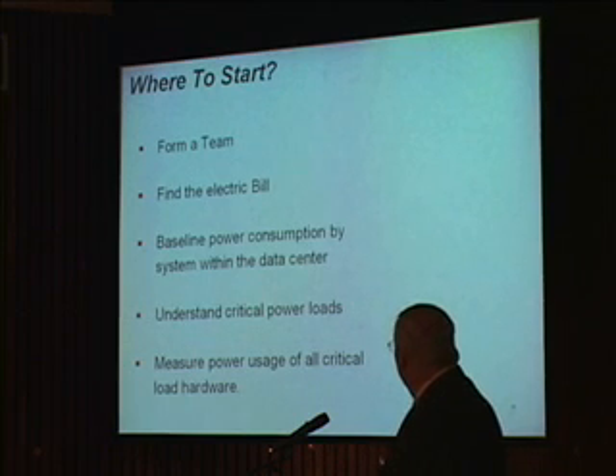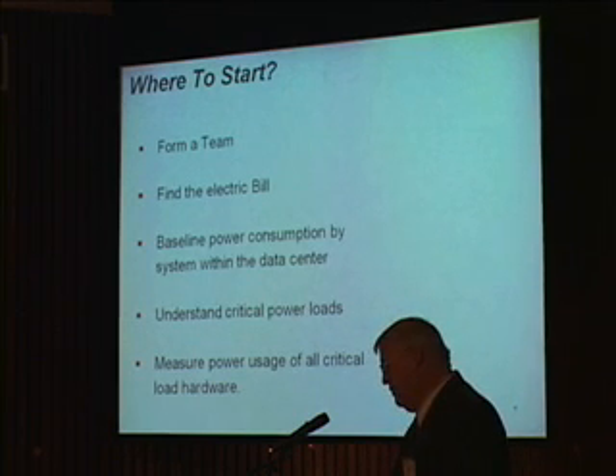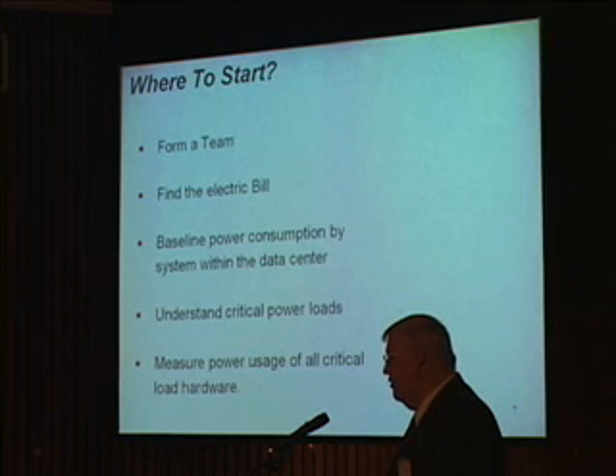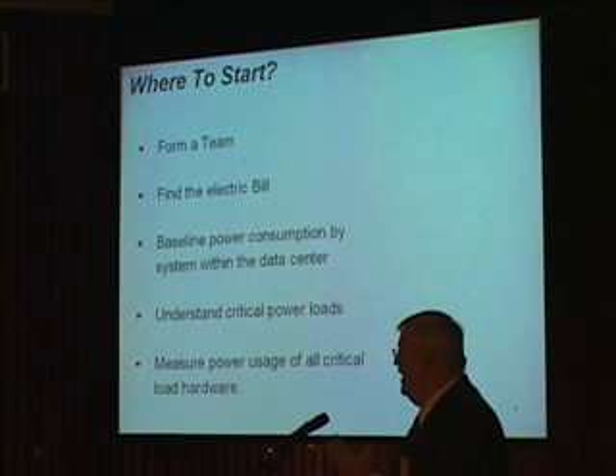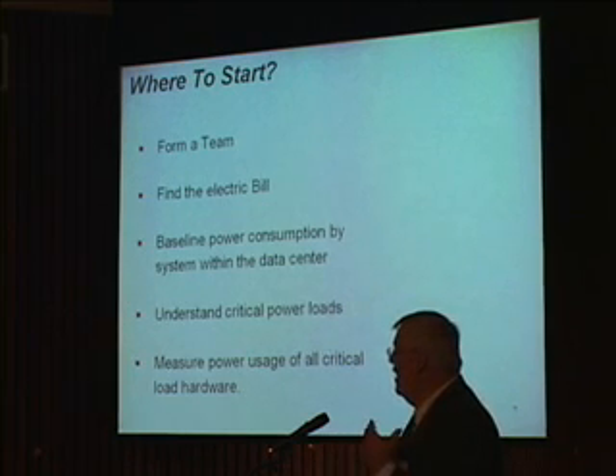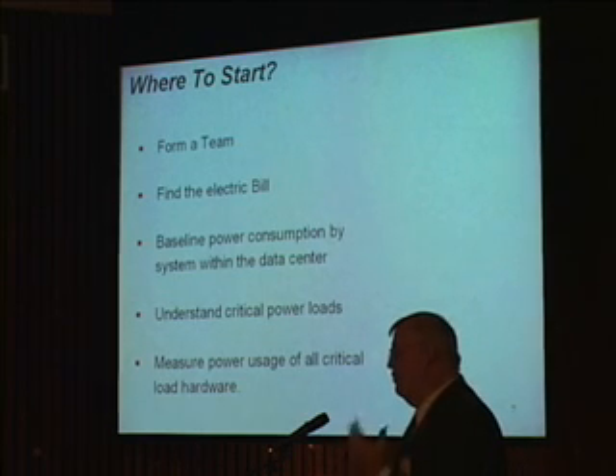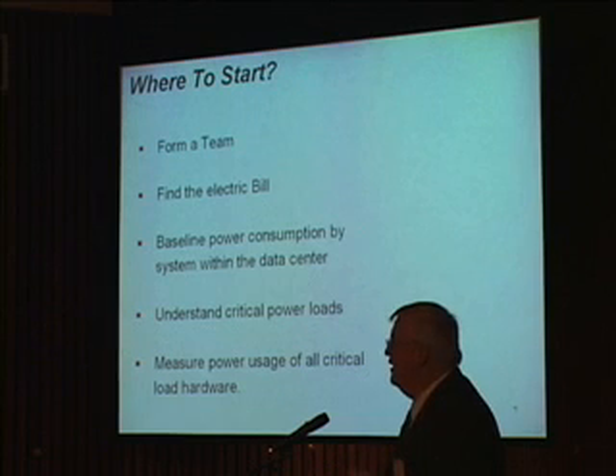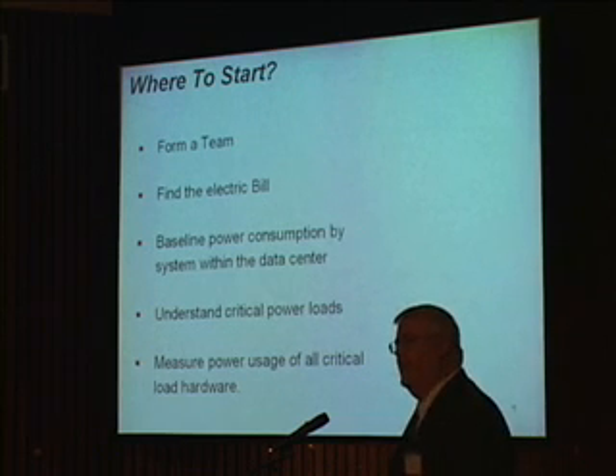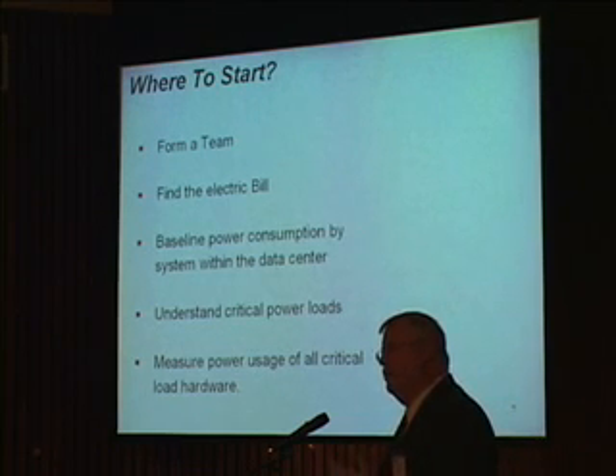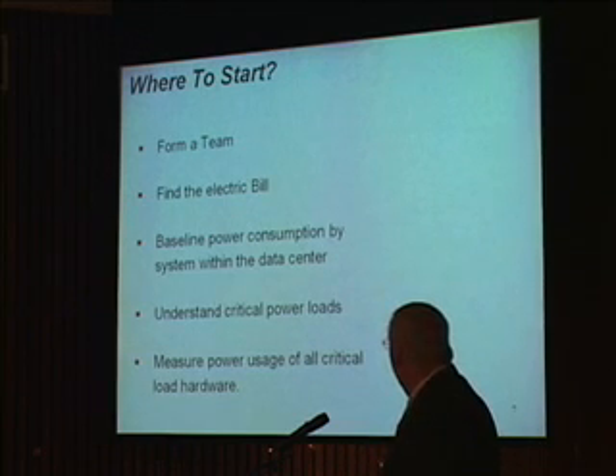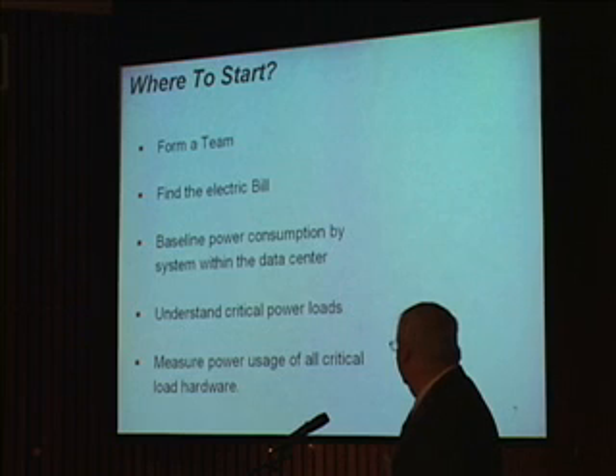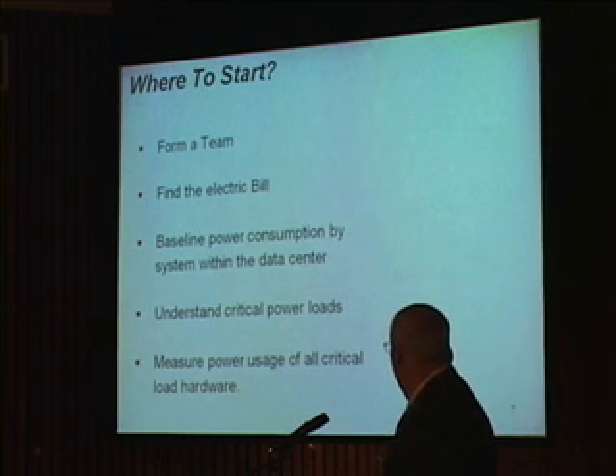Then we baseline our consumption. There's two ways we measure power. This is a standalone building, so I get the power, I know how many kW per hour we're using per month, and what the bill is. Then you have to talk about the data center itself, everything behind your UPS system, because that's really what you're measuring, your critical power. So we had to go out and understand what those critical loads were and measure them.